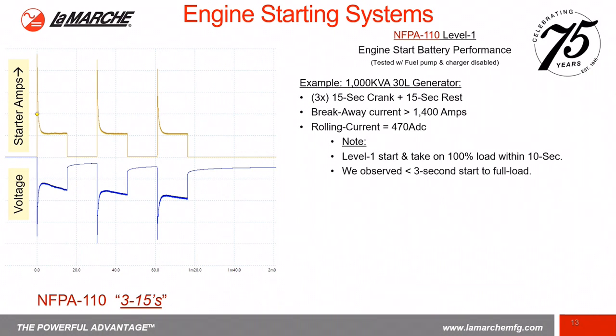Here's a scope shot basically of a 3 cycle start per NFPA. Generators start within 3 crank cycles, duration of 15 seconds. Now, as you'll see during the starting, the starter can draw 1400 amps, which is called the breakaway current. Once the breakaway current has passed and the engine has started cranking, the rolling current could be as much as 470 amps. As you can see, that's a lot of amps that the battery needs to support.